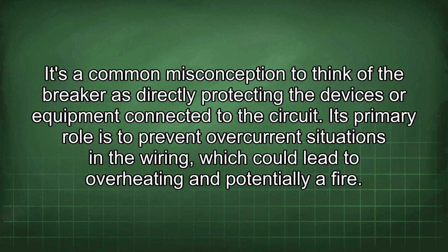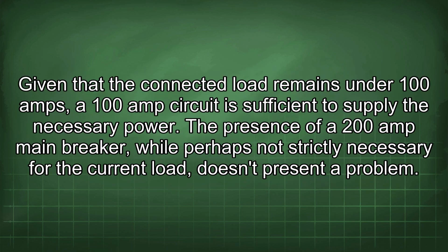It's a common misconception to think of the breaker as directly protecting the devices or equipment connected to the circuit. Its primary role is to prevent overcurrent situations in the wiring, which could lead to overheating and potentially a fire. Given that the connected load remains under 100 amps, a 100 amp circuit is sufficient to supply the necessary power.